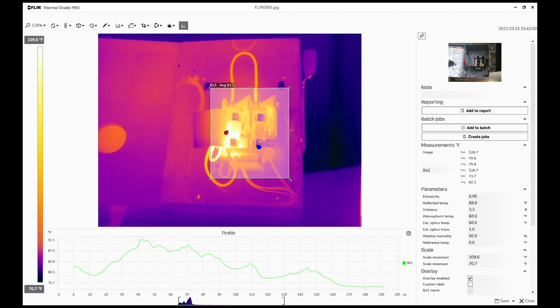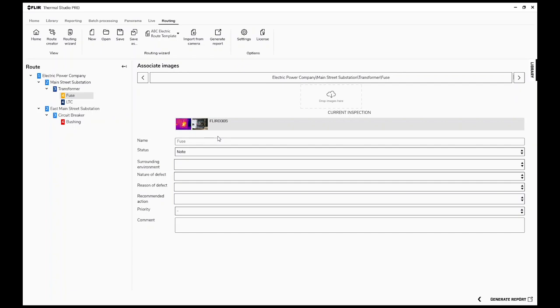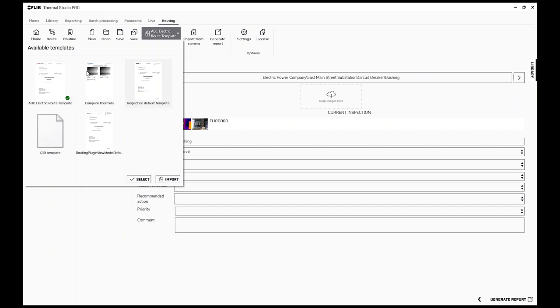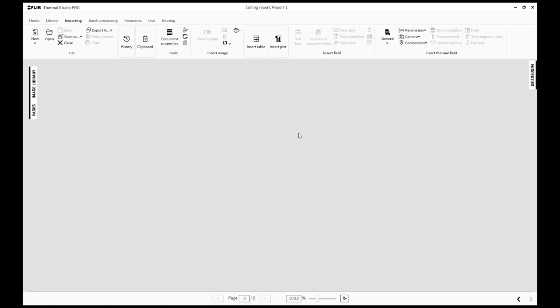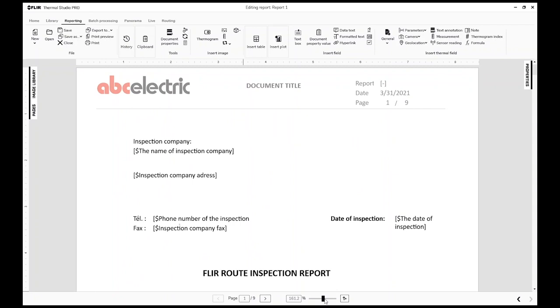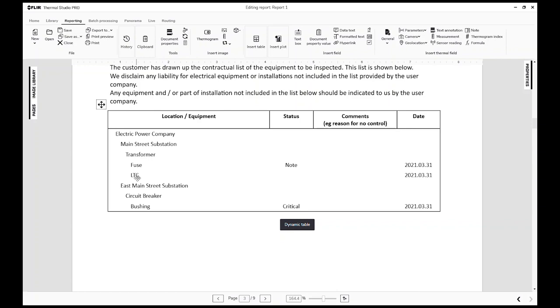If I want to edit the fuse image and add measurement tools, I double-click on it. I can add a rectangle around the entire fuse — red indicates the hot spot and blue indicates the cold spot — so we know exactly where the hot and cold spots are. I save and close, and all those edits are stored in the metadata file. From a template perspective, I'll select the ABC Electrical template, which will take these three images and bring them into the report.